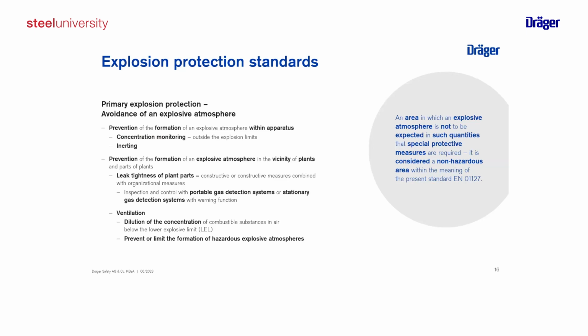If we want to concentrate on the outside of the equipment or the plants, so then we speak about explosive atmosphere in the vicinity of plants or parts of the plants, then we have the possibility by the design, as mentioned before, to have a tightness installation, and there we have different levels of tightness. It can be constructive and durable, so it means we can be sure that it will not leak to the outside, but in most installations we have to consider pumps and valves. They are only tight in combination with organizational measures, and this could be by frequent inspection using a portable gas detector to control the atmosphere, or you use a stationary gas detection system which is installed there and is permanently observing the atmosphere.